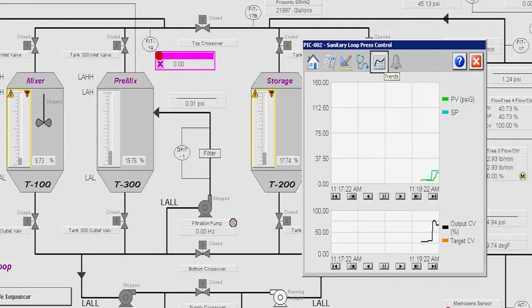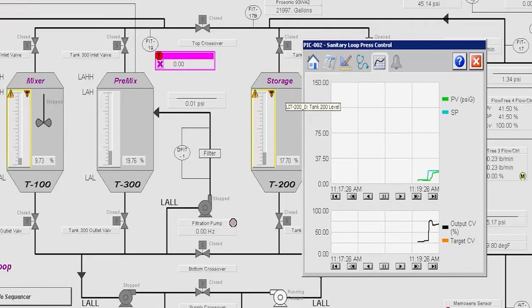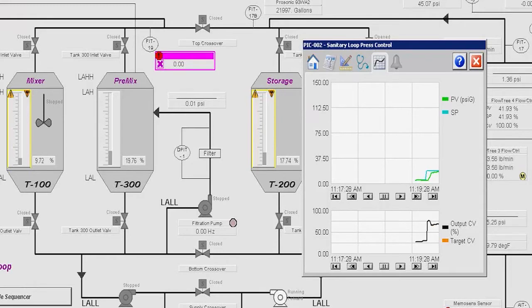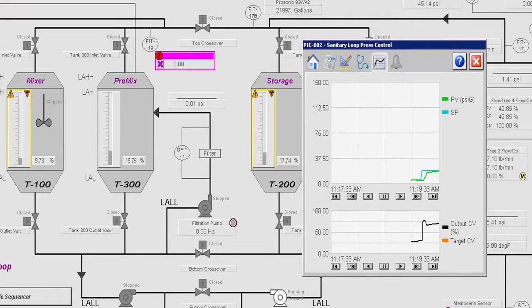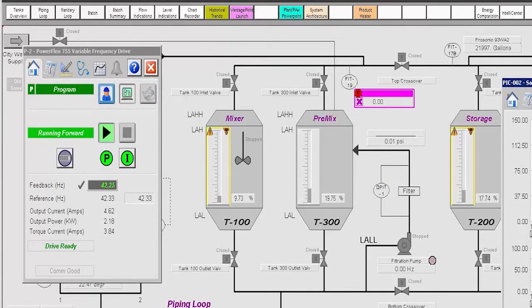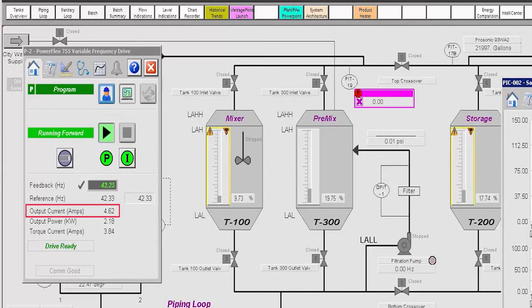On the trend pane of the PID faceplate, we will see the set point step to the new value and the process variable reach the set point value as the motor speed adjusts in response to the PID calculations. When the process variable has reached the set point, you can see the actual power required to achieve this pressure.